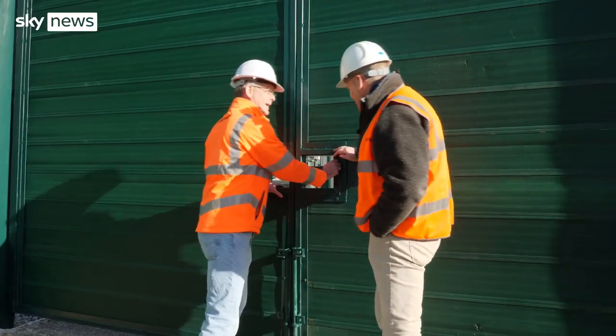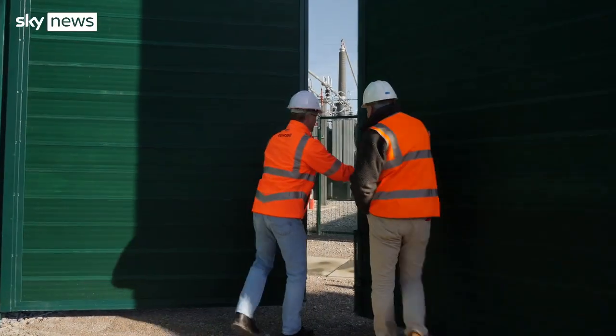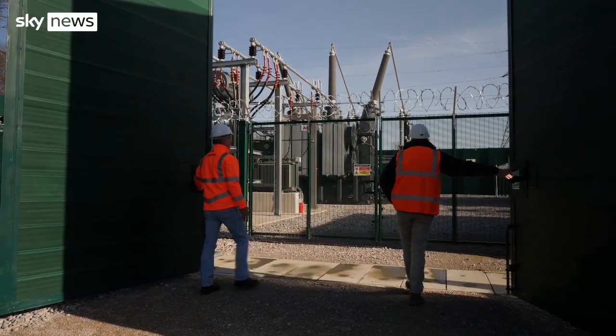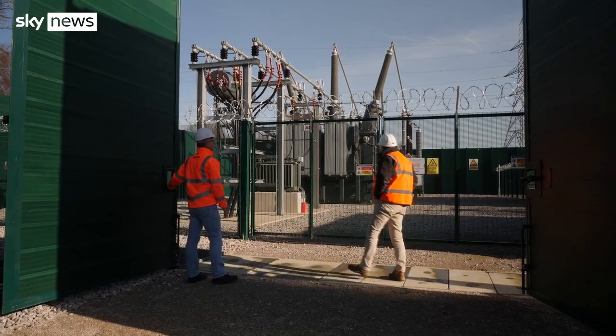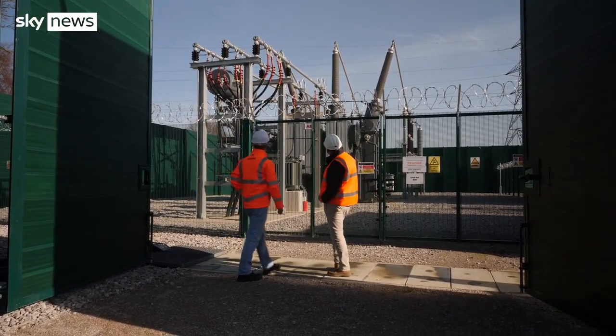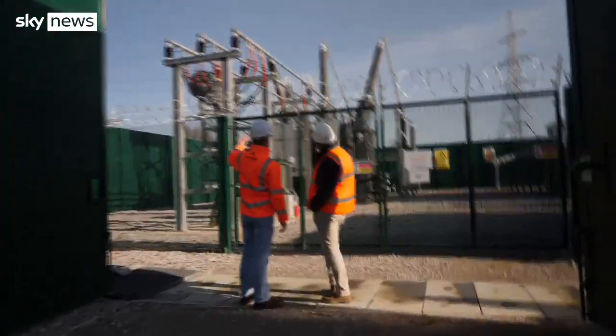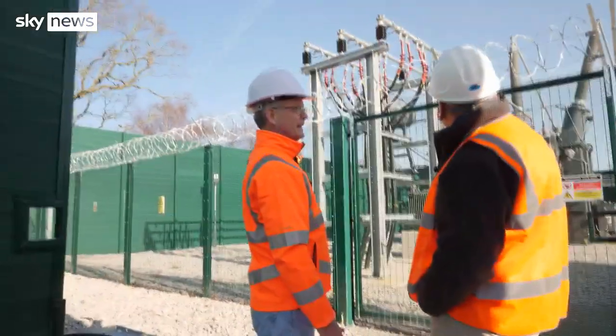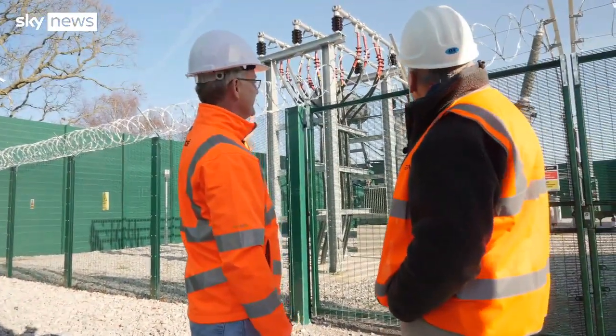What's in here? Well, this is where this battery site connects to a supergrid transformer and onto the national grid. That's a hell of a connector you've got there. So this is connecting up to 275,000 volts, and this is the largest transformer to be connected to a battery storage site in the UK.